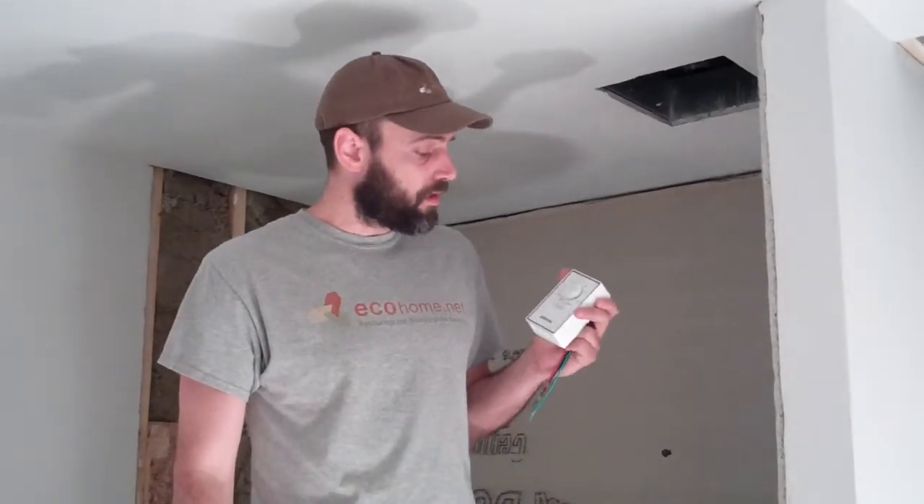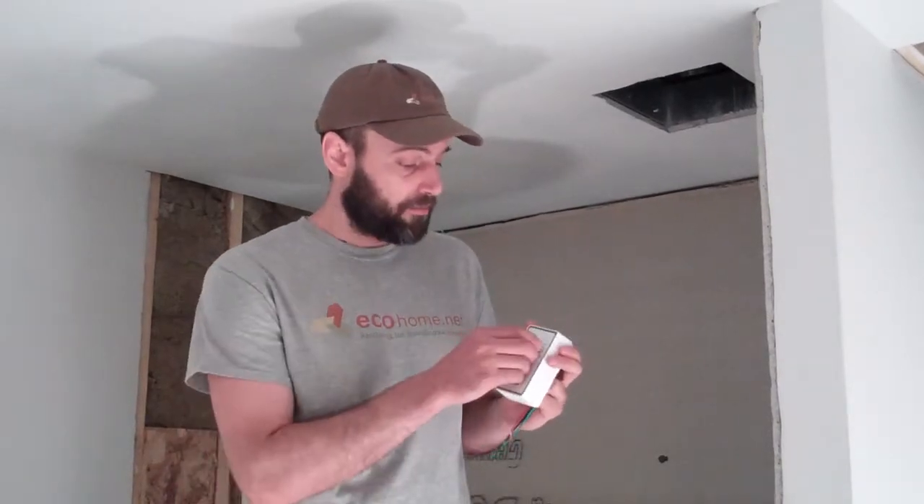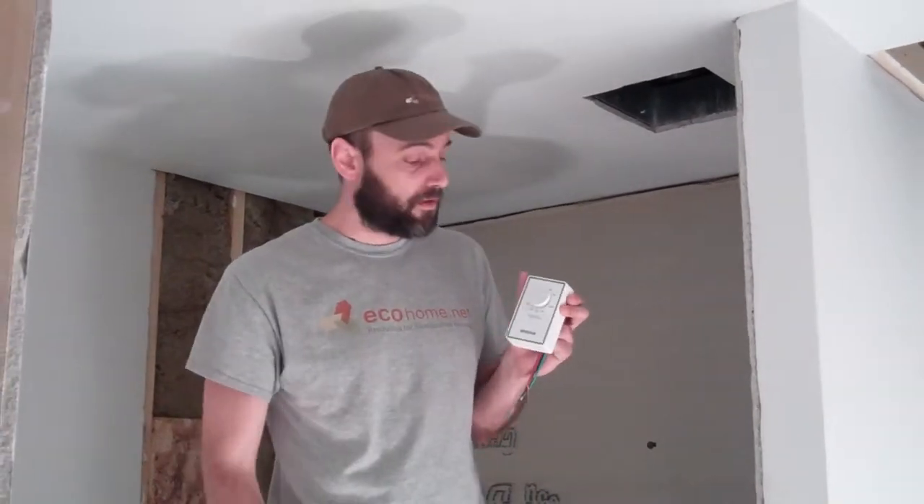Here in the bathroom we're installing NuTone exhaust fans that are Energy Star certified, but also very quiet — they've got a one sone rating — and that'll mean that people will probably use them more than if you're using just noisy bath fans; there's nothing worse. We're also pairing it up with a dehumidistat that can go on when you want it to, but you can also set the humidity level at, say, 50%, and it'll go on automatically when the humidity levels in the bathroom get too high.